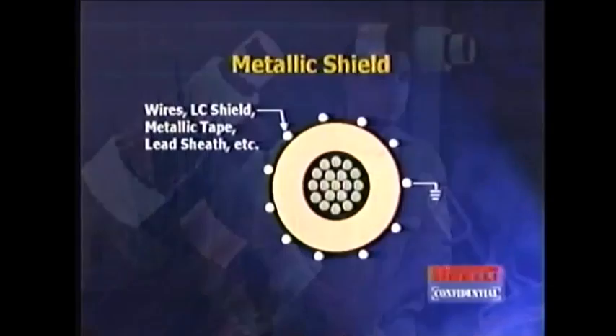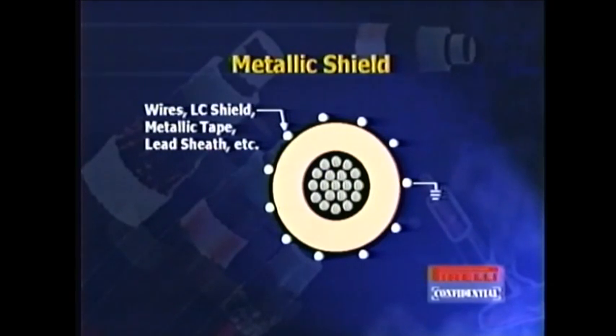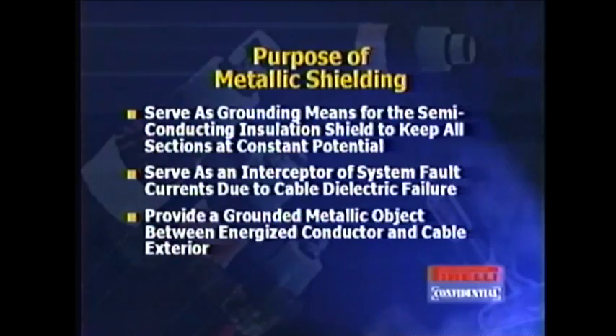So to avoid this situation, what we do is we provide a ground, some type of a grounded conductor around the insulation shield. In this case, we're showing the standard concentric neutral shield, which is a typical URD cable. This consists of heavy copper wires, which serve multiple purposes. One of the purposes is to keep the shield, of course, at a constant potential. This can be achieved by either a fine wire shield, a copper tape shield, or a heavy wire shield, essentially any grounded conductor.